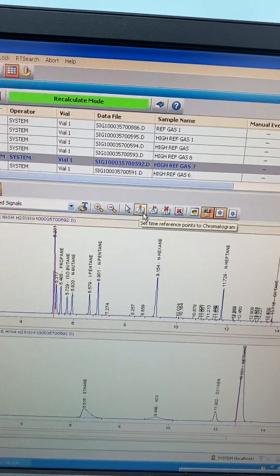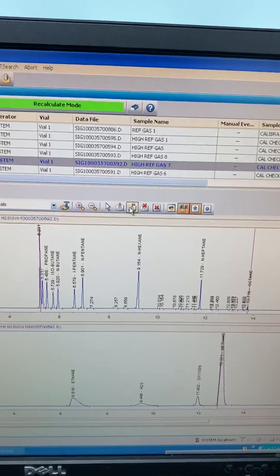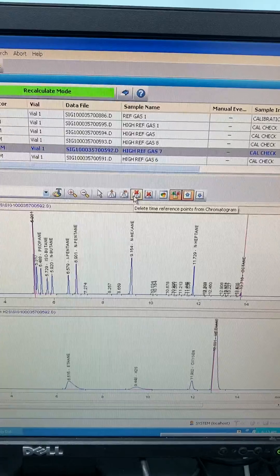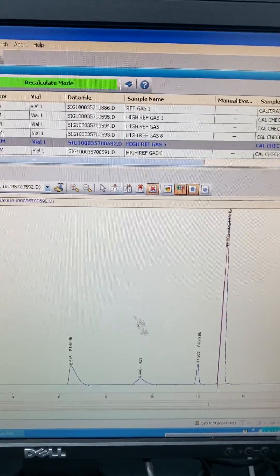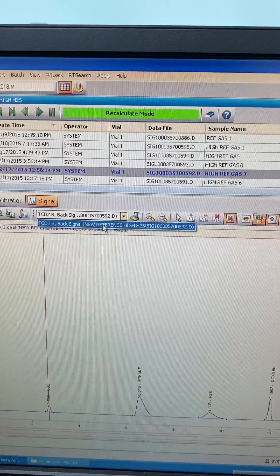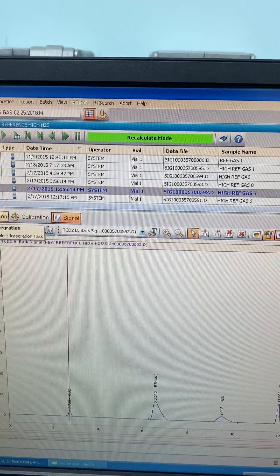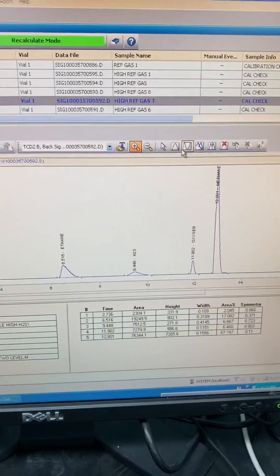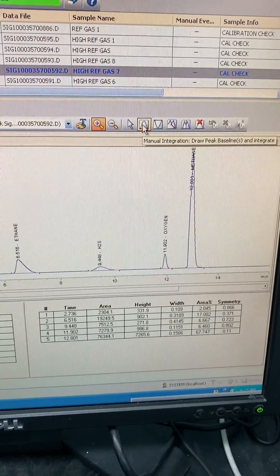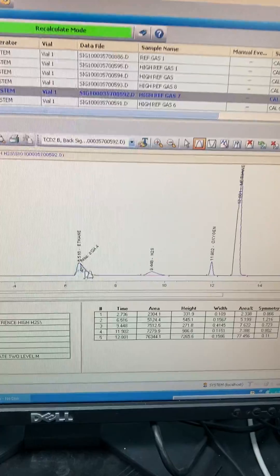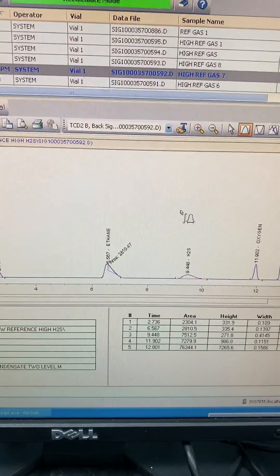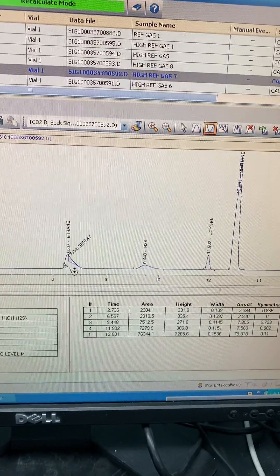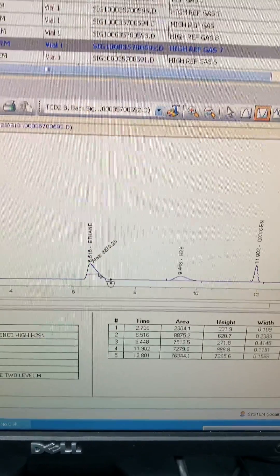The first one, it's like set this time for reference point. This is like the initial peaks. Usually it's here. And the other one move to the reference here to delete the time reference from the chromatogram. The other one, delete the object. If I press here and I click, it will be deleted the detector that I already working on, which was the FID. So here, for the integration parameters. This one, if you want to make manual integration for the peak itself. Like if I press, I say no, I need this peak from this one. So that means this become now small peak and I can make another peak here. So select each one or which one you want.